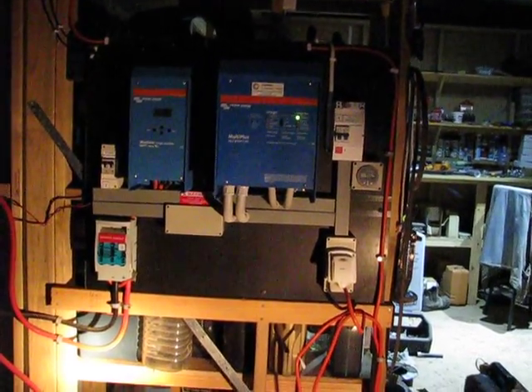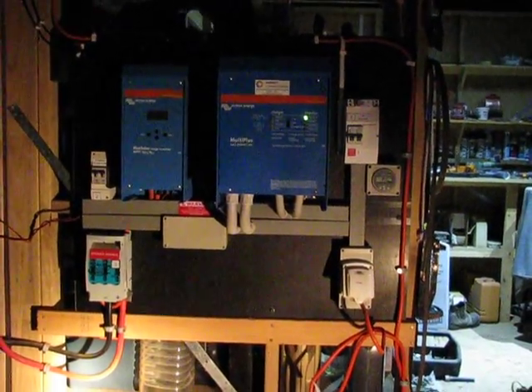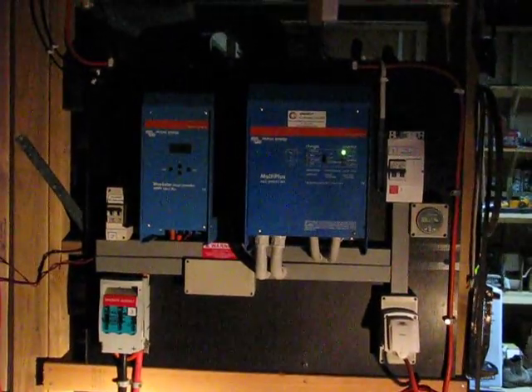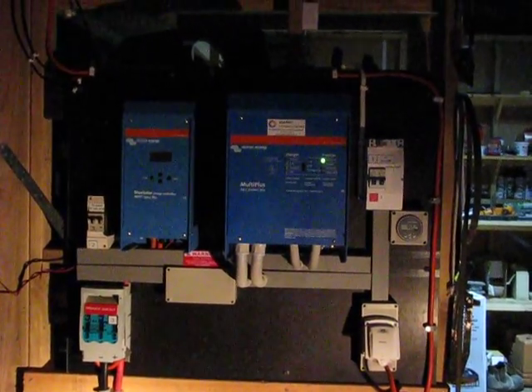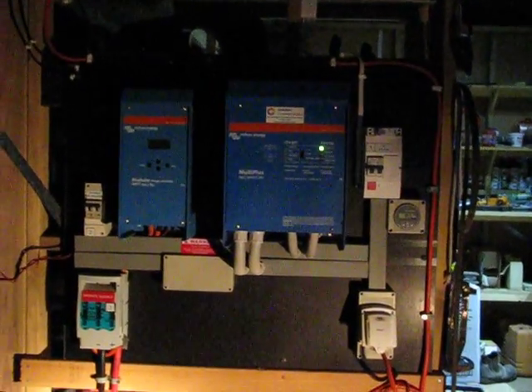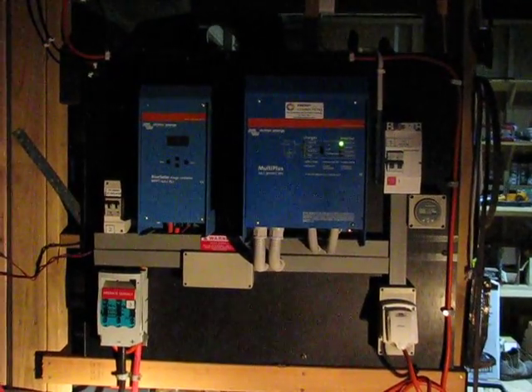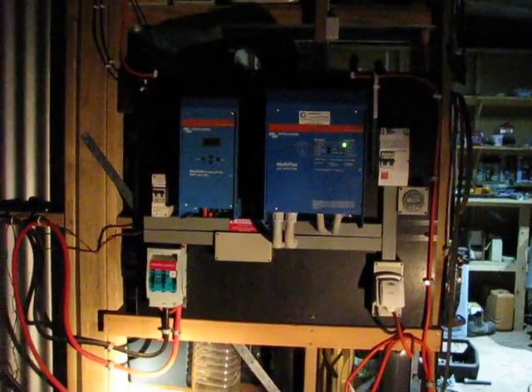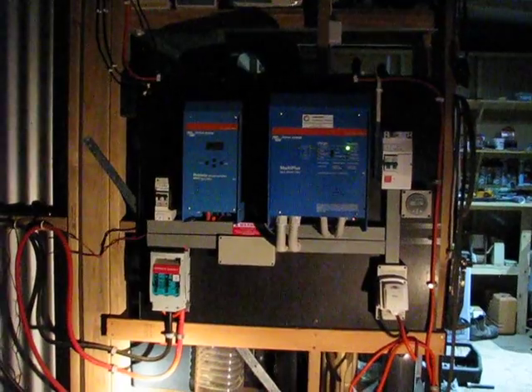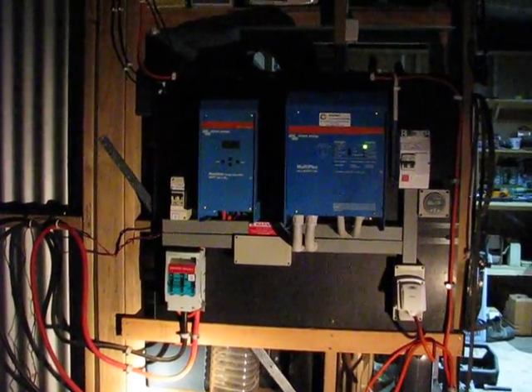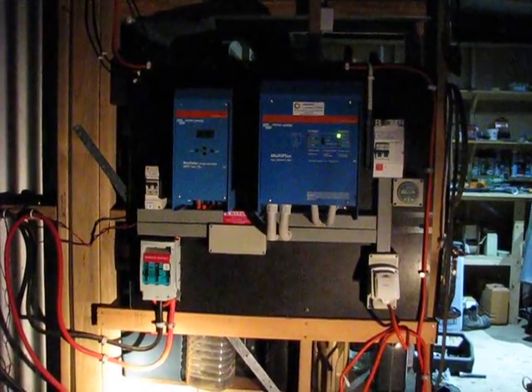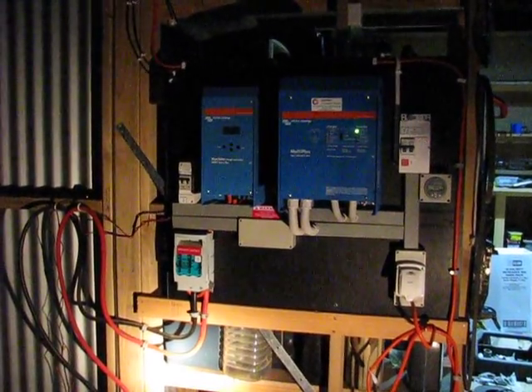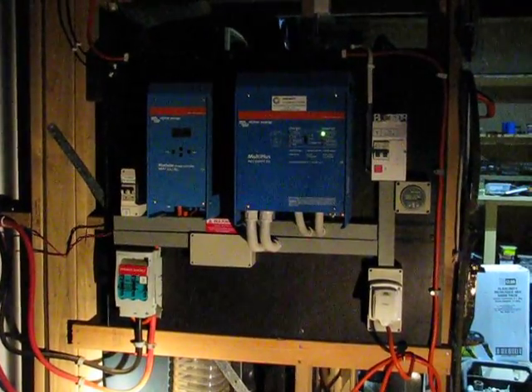I had a 7 kVA Honda and a diesel generator that's a bit erratic. When I put this 3 kilowatt system in, most inverters require what's called a steady hertz rate. The bigger inverters especially require a hertz rating, meaning the power put out of that generator is stable. My 7 kilowatt Honda, the rating goes up and down like a yo-yo. It doesn't affect the welder and stuff, but if you're powering up sensitive equipment like your controllers and inverter, you need a generator that's compliant.